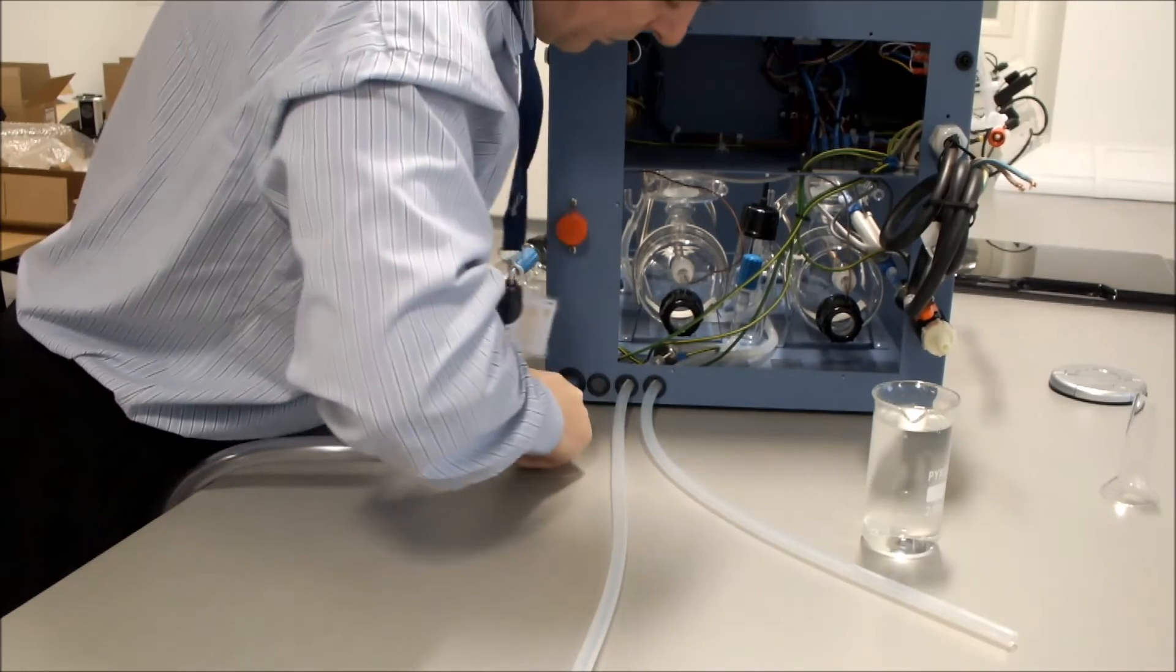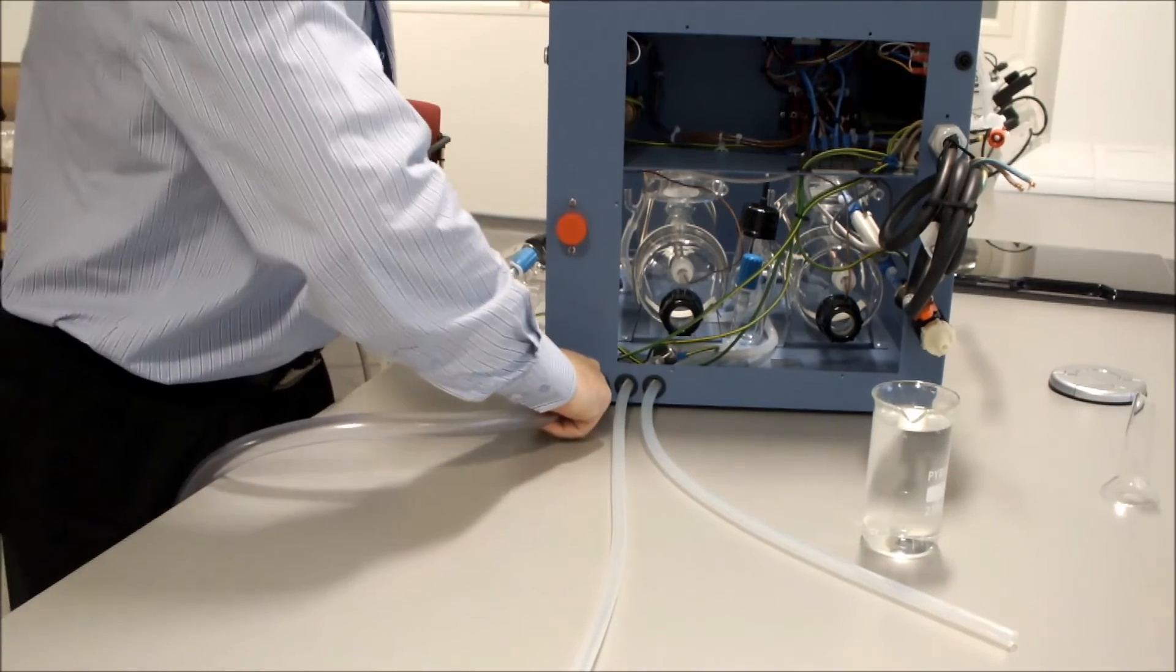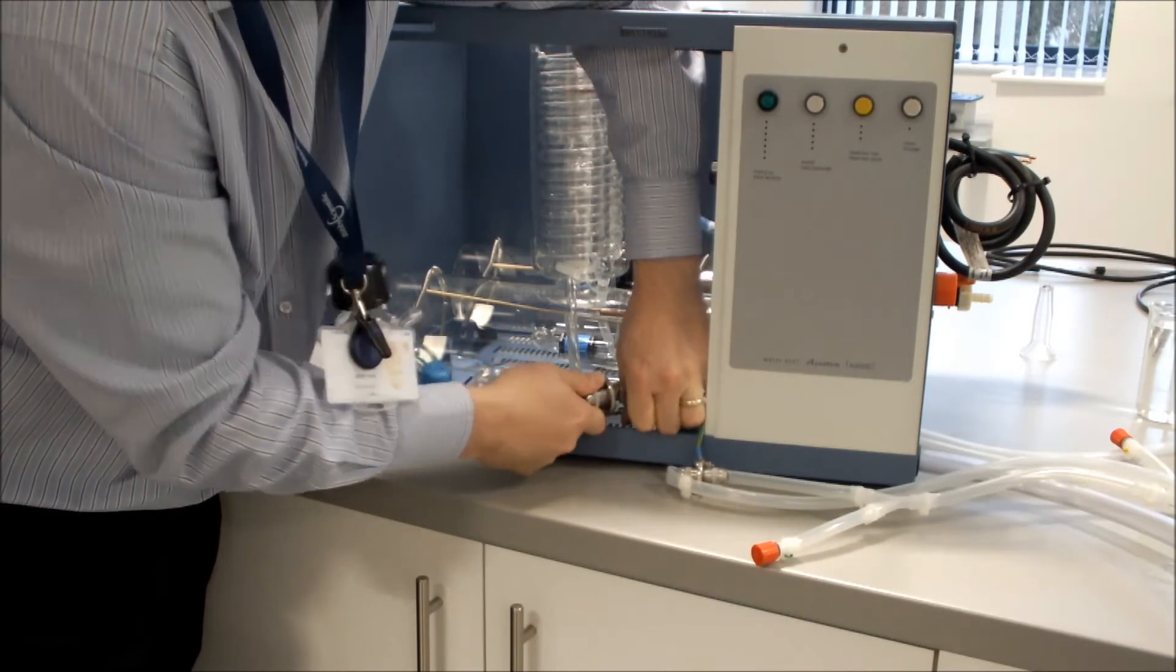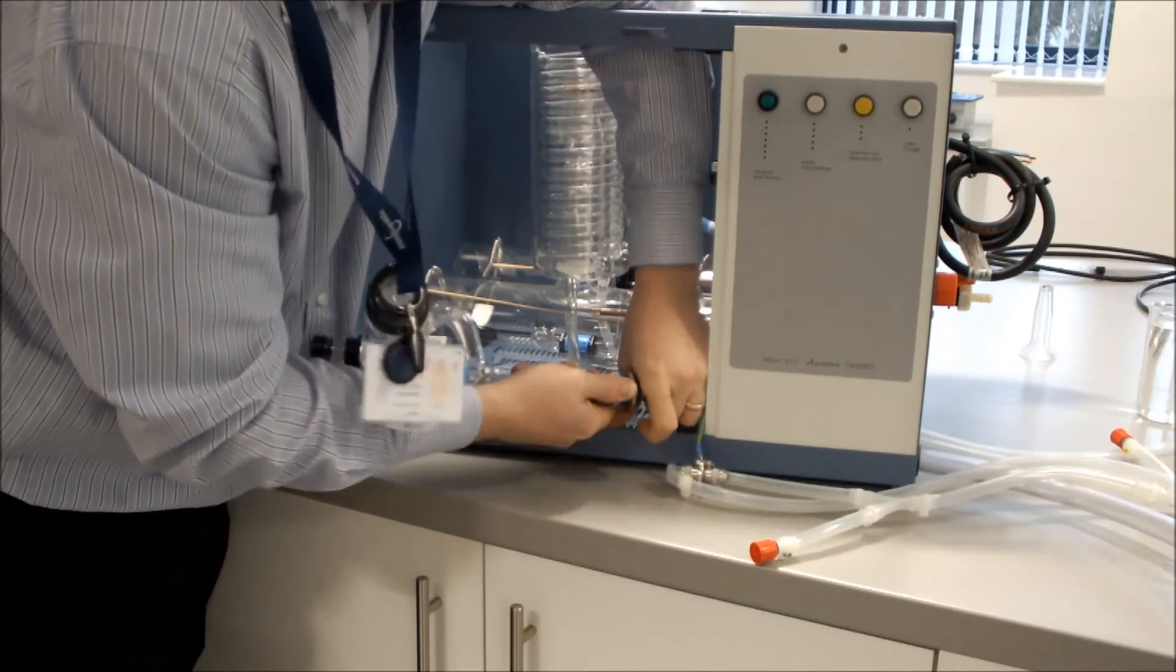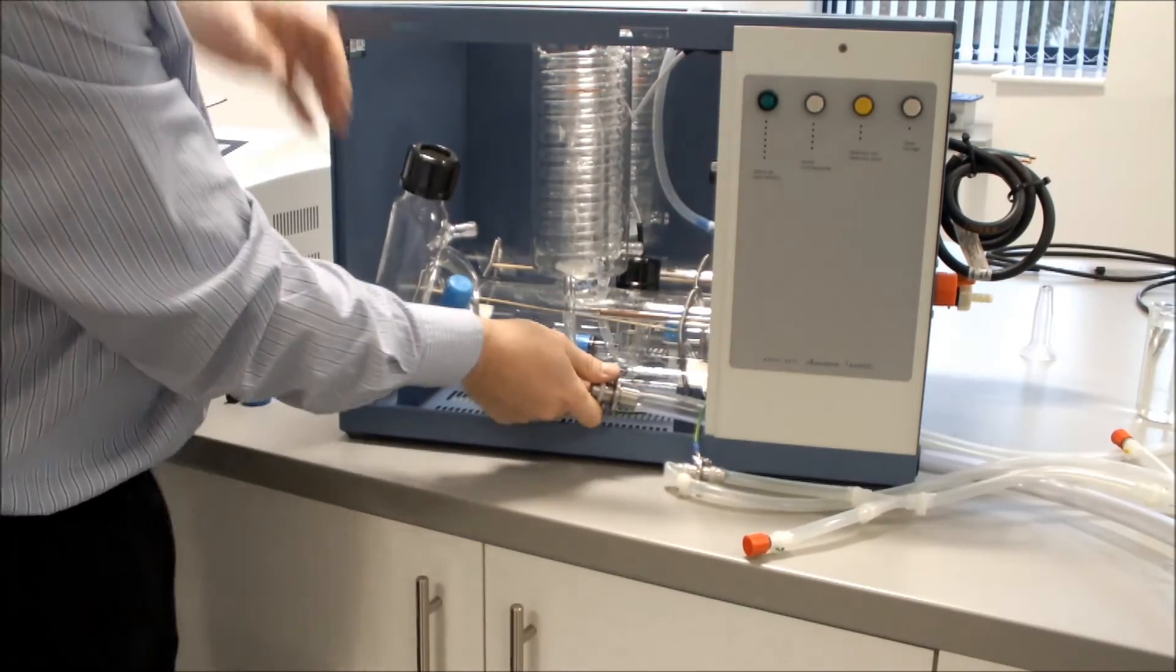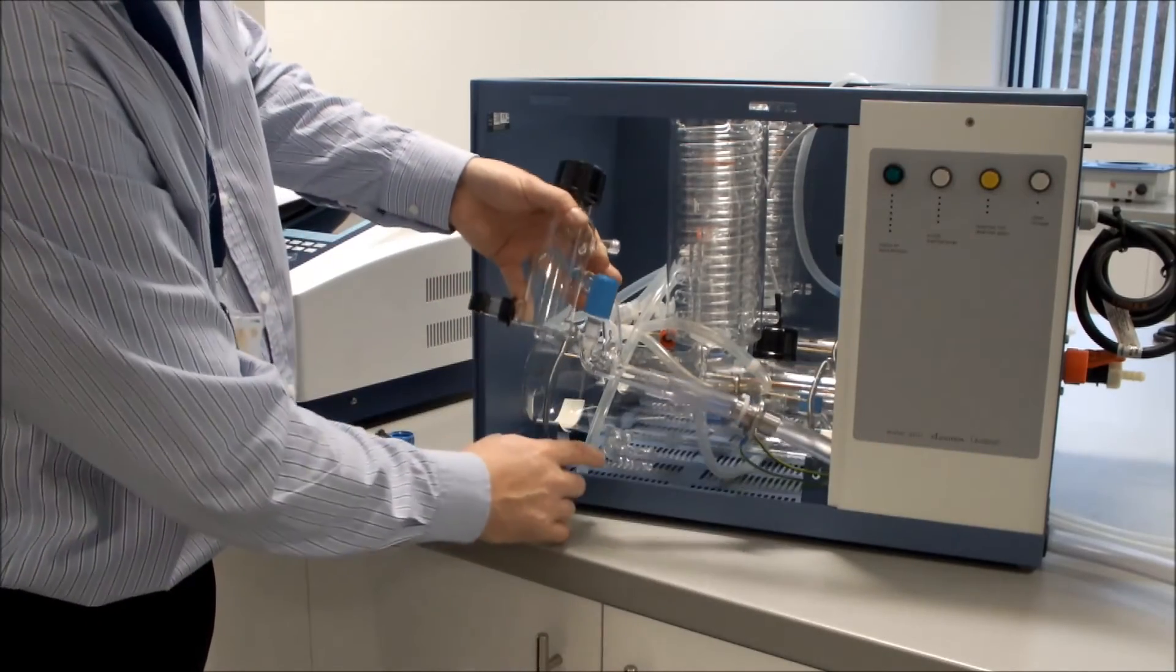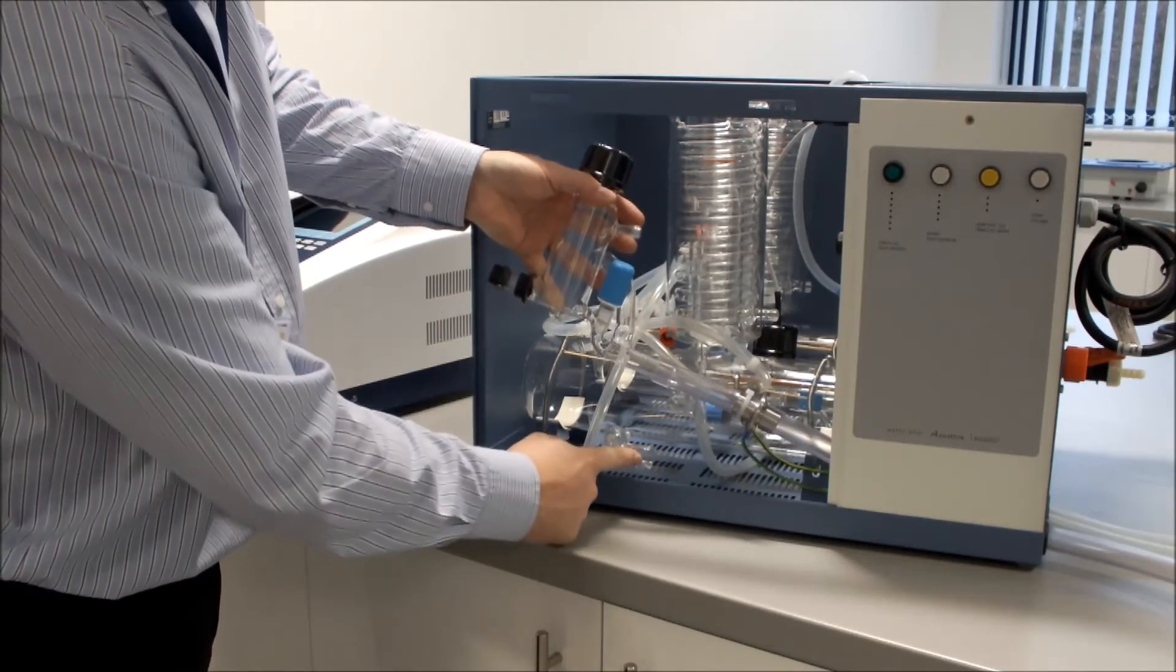We then insert the hose to the largest hole like so. It needs to be pushed in approximately one foot into the unit itself. We then connect our 16mm hose to our 16mm earth spigot hose assembly like so and again this is tie wrapped around here.